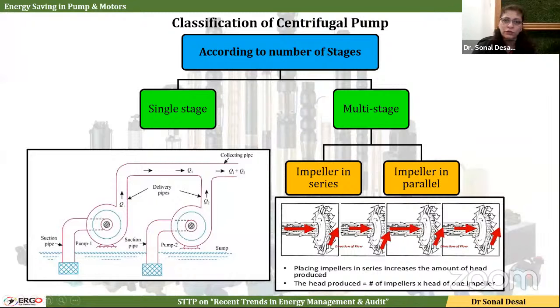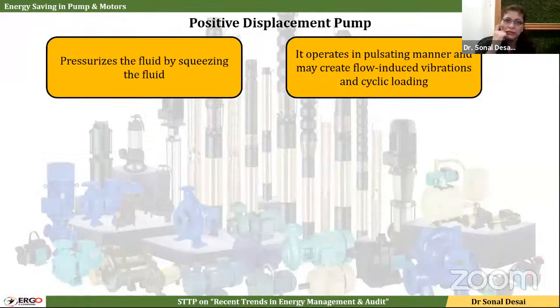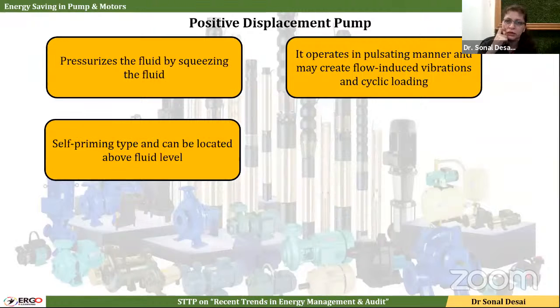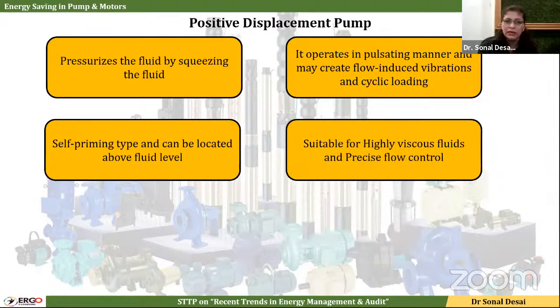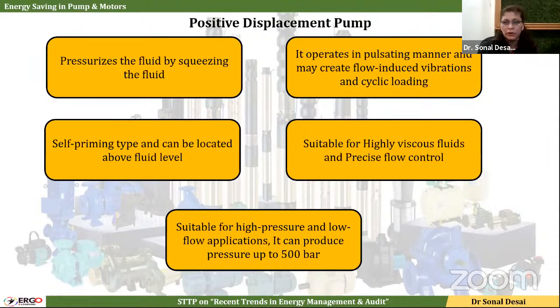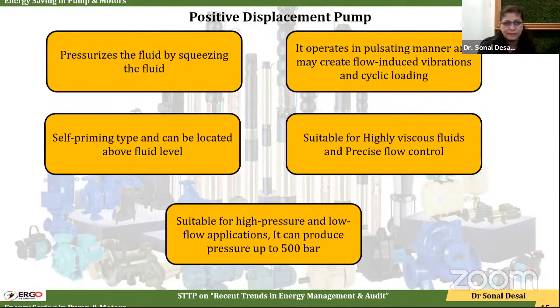Pressurizing and squeezing of fluid takes place in a positive displacement pump. It's not like a centrifugal pump. It operates in a pulsating manner, so it may create flow-induced vibration and cyclic loading. They are self-priming and can be located anywhere. The advantage of positive displacement pumps is that they need not always be submerged, and they can also handle viscous fluid. So for particular industrial applications, these are being suggested.